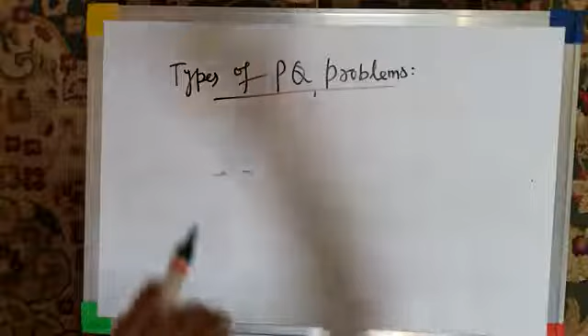I repeat, power quality problems are broadly of two types: voltage and current variations and events. Now, voltage and current variations are further sub-classified into voltage magnitude variation, voltage frequency variation, voltage fluctuations, voltage flicker, current magnitude variation, current phase variation, current and voltage imbalance, and voltage distortions. And events are classified as transients, interruptions, voltage sags or under voltages, voltage swells or over voltages, and voltage step variations.